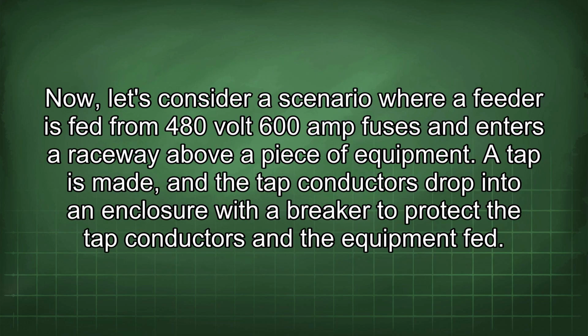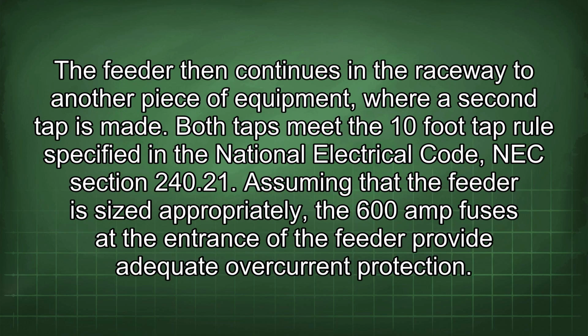Now, let's consider a scenario where a feeder is fed from 480 volt 600 amp fuses and enters a raceway above a piece of equipment. A tap is made, and the tap conductors drop into an enclosure with a breaker to protect the tap conductors and the equipment fed. The feeder then continues in the raceway to another piece of equipment, where a second tap is made. Both taps meet the 10-foot tap rule specified in the National Electrical Code, NEC Section 240.21.